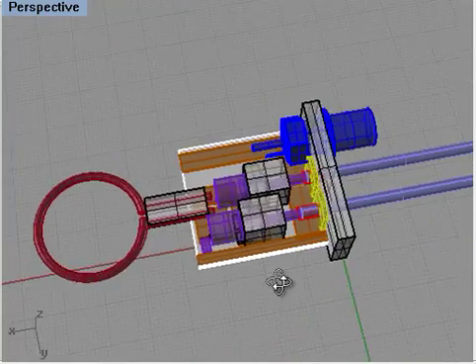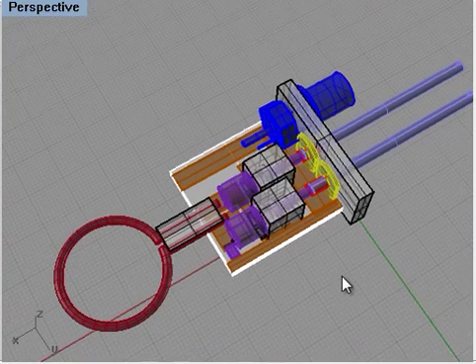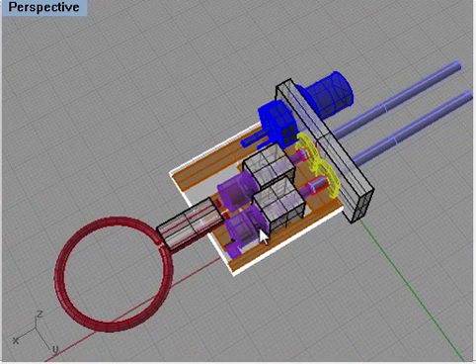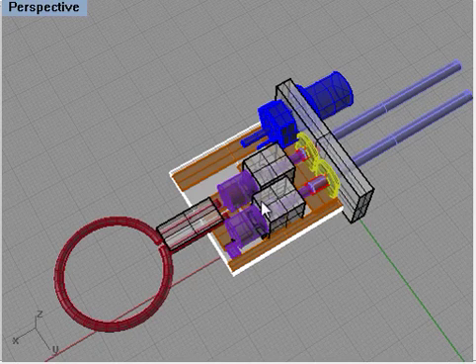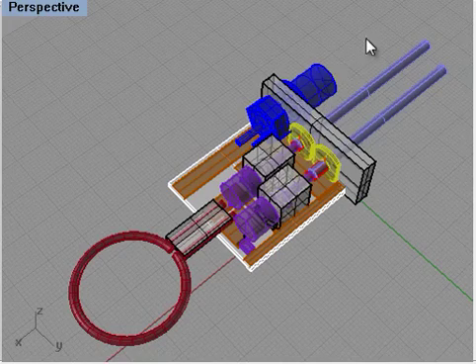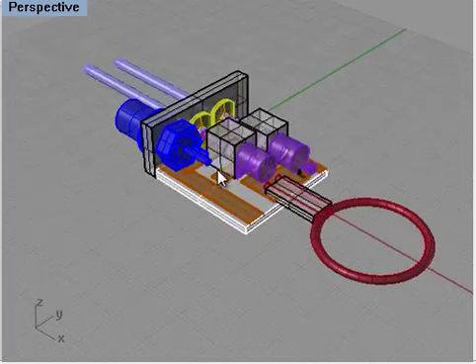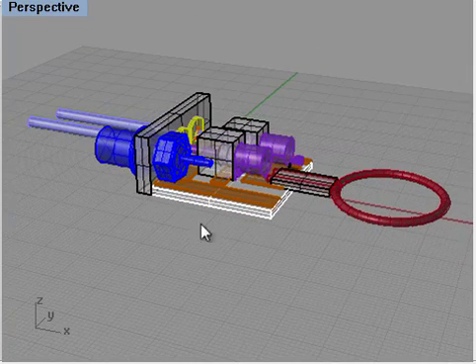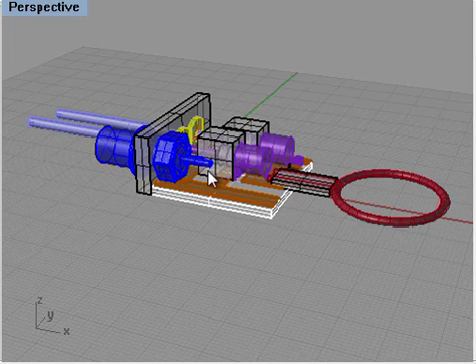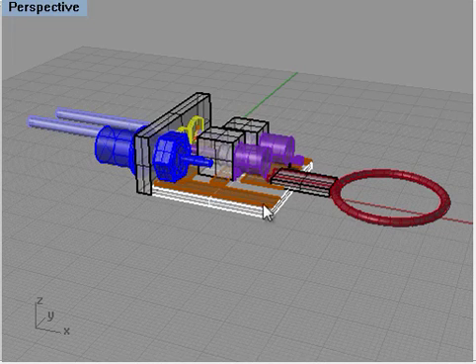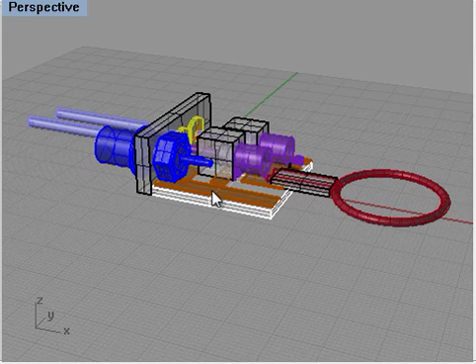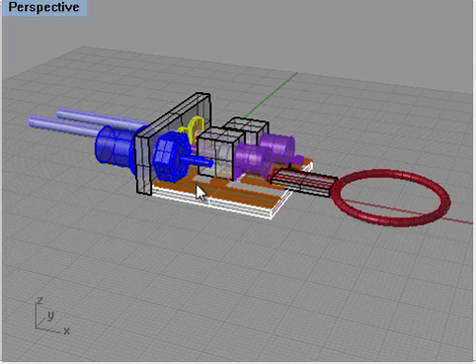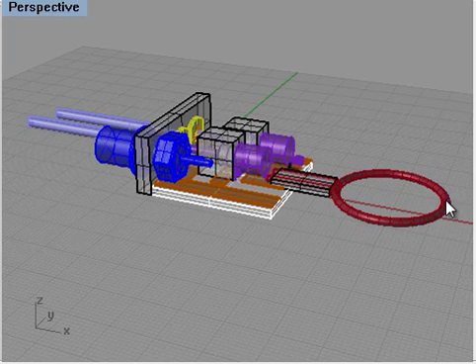So basically, what I wanted to show you is just the matching network. So you have the two capacitors here. Here's the BNC cable would come in here, and this eventually would be, although it's not shown here, as being soldered down. This little piece here of this connector would have a wire soldered to this kind of a copper bus, so that would carry the power from the RF amplifier onto the circuit and eventually into the coil itself.